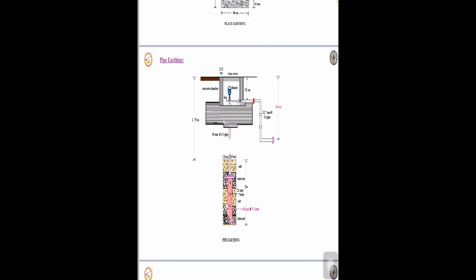Also we can observe the difference between plate and pipe earthing here. Everything remains the same, except that here a GI pipe with a few holes at its lower end is buried to a depth of not less than 2 meters, and again 0.6 meters away from any other foundations. Normally the plate is replaced by the pipe here, and the pipe should be 2 meters long with 30 to 40 mm diameter, or 1.37 meters long and 51 millimeters in diameter. Whenever longer pipes are used for dry rocky soils, alternate layers of common salt and charcoal, about 30 millimeters and 80 millimeters thick respectively, are spread, as you can observe here.